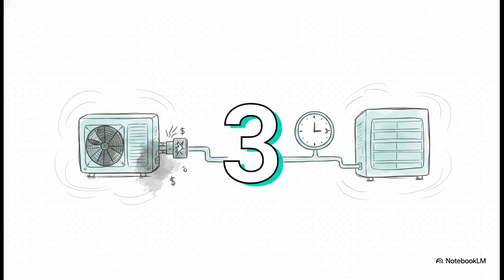Listen to this. After your AC shuts off, or if you lose power and it suddenly flickers back on, you absolutely must wait at least 3 minutes before restarting the system. Why? Because you have to let the refrigerant pressure equalize between the high and low sides of the unit. Forcing it to start too soon strains the compressor against massive internal pressure. It's a simple mistake that can blow the compressor and cost you thousands of dollars. Just wait the 3 minutes.